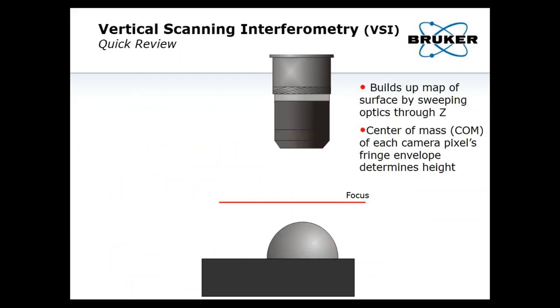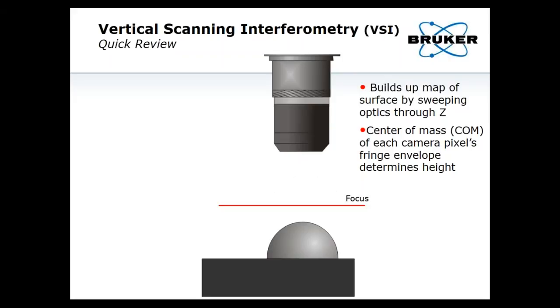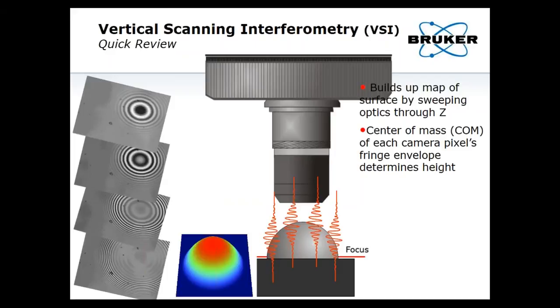How do we make measurements? We sweep the optics through the sample. As your sample traverses the focal plane, you build up a series of images. Those images are combined in the computer to build a 3D surface. As you sweep through the surface, each pixel in the camera will start to modulate, and the center of mass of the modulation envelope is what determines where the pixel is assigned in height. By doing that over the entire detector array, you get the full image built up and a 3D surface.